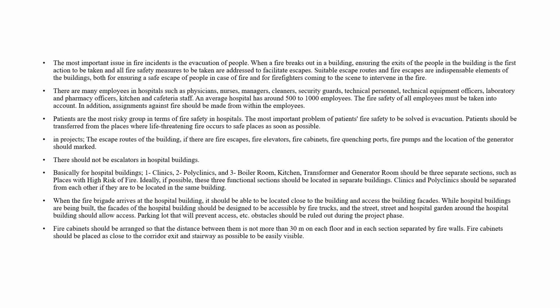In projects, the escape routes of the building, fire escapes, fire elevators, cabinets, quenching ports, fire pumps, and the location of generators should be marked. There should not be escalators in hospital buildings. Basically, for hospital buildings, clinics and polyclinics, the boiler room, kitchen, transformer, and generator room should be three separated sections, as places with high risk of fire. Ideally, if possible, these three functional sections should be located in separate buildings. Clinics and polyclinics should be separated from each other if they are to be located in the same building.